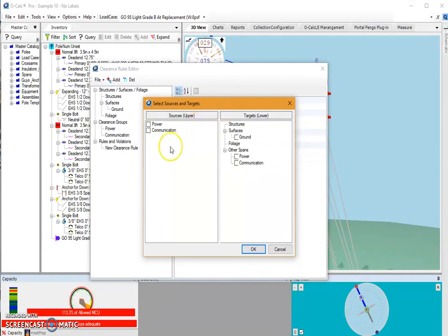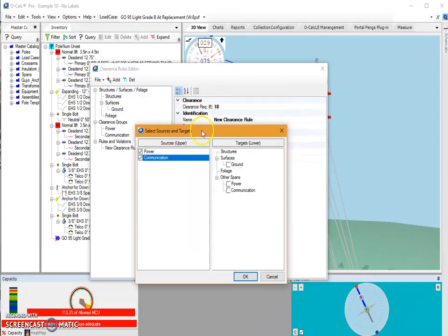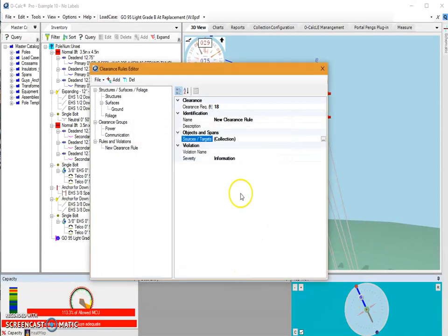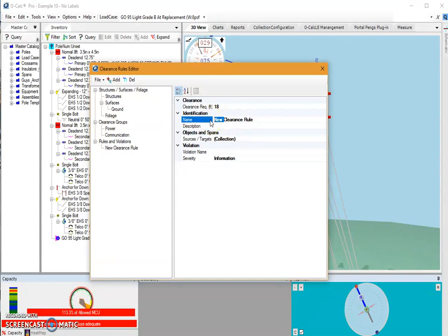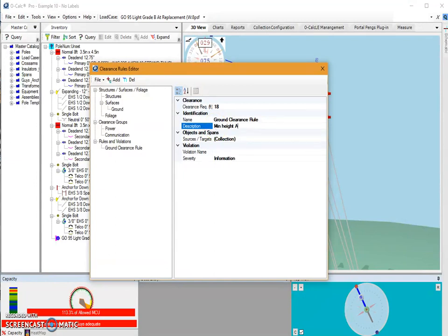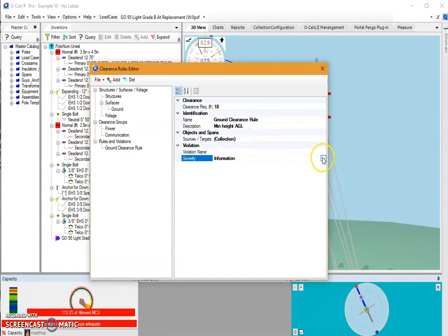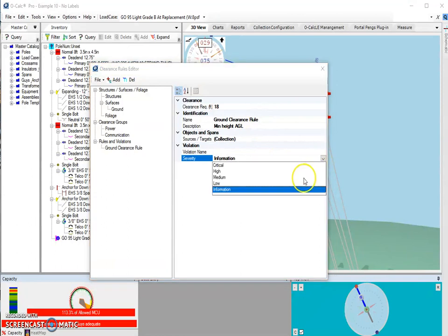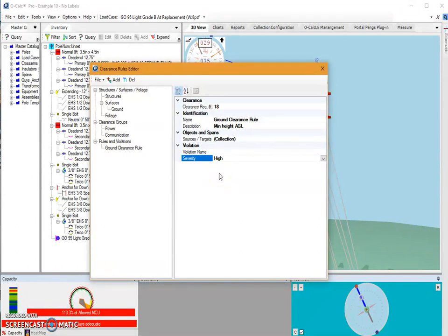So I'm going to say that my power and communication, my upper targets, have to be at least this 18 feet above the ground. So I'm going to hit OK. I'm going to give this rule a name. I'm going to just call this one ground clearance rule. And for the description I'll put in minimum height above ground line. And as far as severity, I will mark this as a high severity violation.